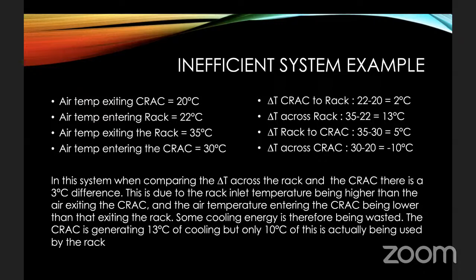And if they only need 22 degrees, then that means I could change the set point of my CRAC, right? So my servers are quite happy with the 22 degrees coming in. So why don't I set my CRAC to 22 degrees? Because in this system, it is not perfect. If I set my CRAC to 22 degrees, what temperature will the air be at the rack? It will not be 22 because we are losing 2 degrees of cooling energy. So it's going to be 24. Now my servers are going to overheat. So effectively, what I'm having to do here is overcool to make up for those inefficiencies. If I could get the air leaving the CRAC and entering the rack to be exactly the same with no delta T between them, 100% of my cooling energy is going into my servers. So simply increasing the set point of my CRAC in this case is not going to help me save money because I'm going to end up overheating my servers. Everyone follow that?